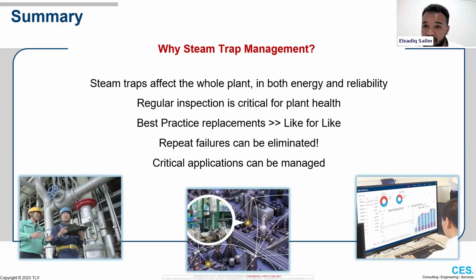So just to summarize, why steam trap management? We know steam traps affect your whole plant. They're like part of your body. You wouldn't go get a health check and not check the whole body. Steam traps are very critical for that. Regular inspection is critical for that. Plant health cannot be ignored for more than a few years and expect a healthy plant. Best practice replacements will always be better than like-for-like replacements, and you can hope that your repeat failures, if any, can be eliminated, and critical applications as well can be managed.